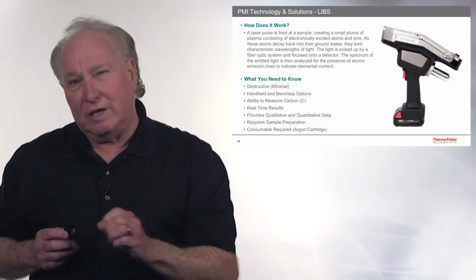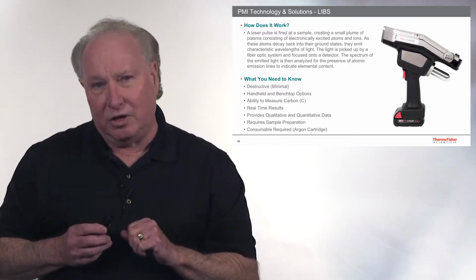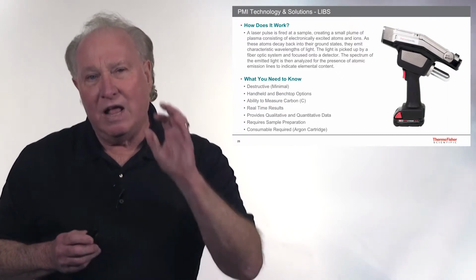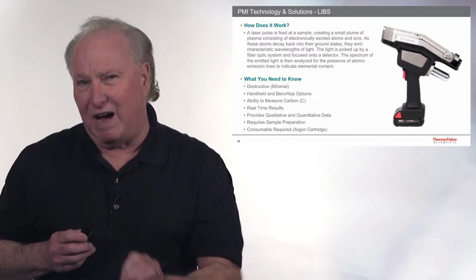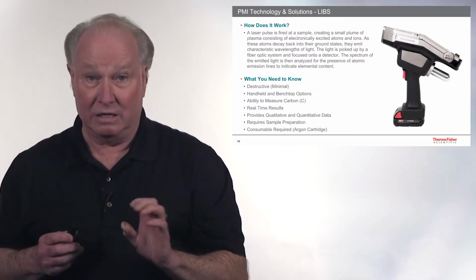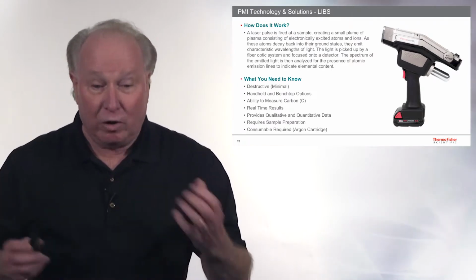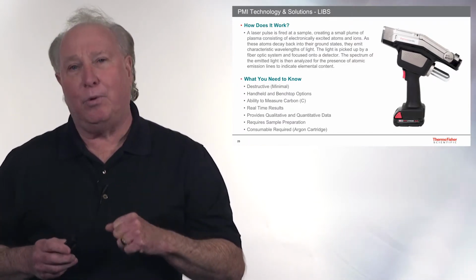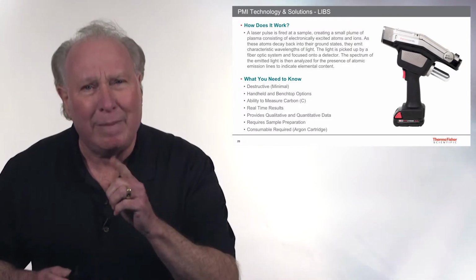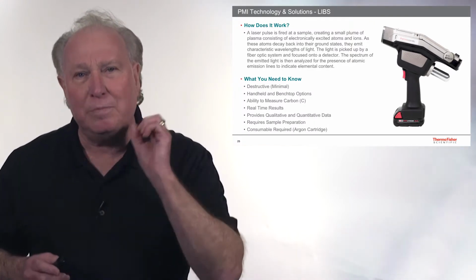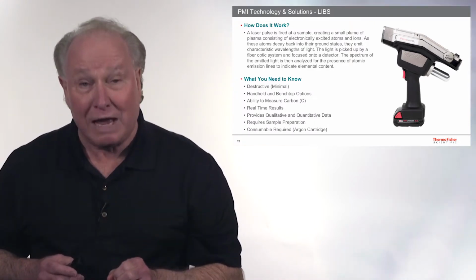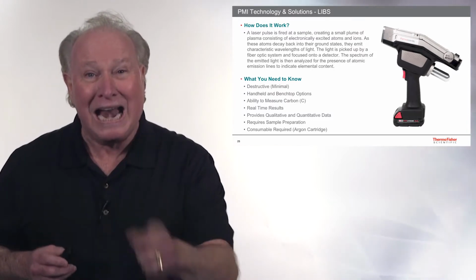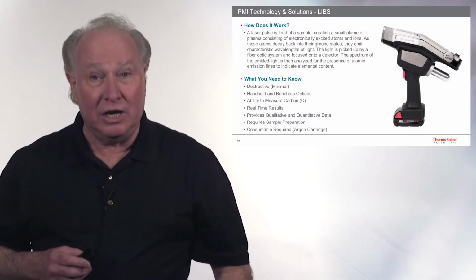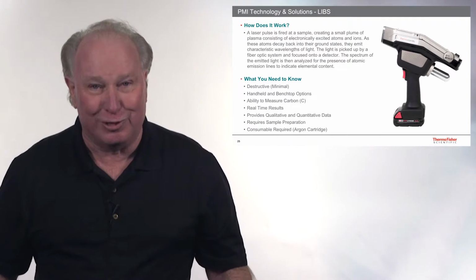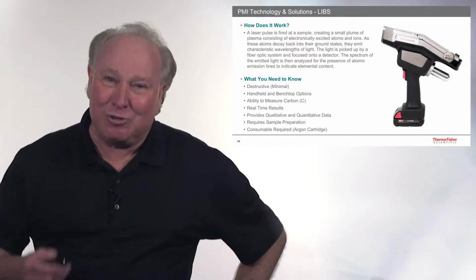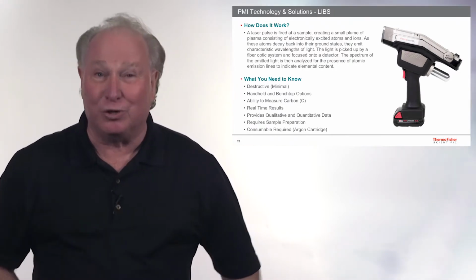Those detectors that detect them, there are 3 in the LIBS devices that are out there. They have charge coupled devices, CCD detectors in them. So they do a great job. Sample prep's very important. The clean argon, I might mention this, argon has to be laboratory quality. You know what that means? 99.999%. If you have any moisture in it, you won't get good results. And buddy, you spend time trying to get low levels of carbon, you want to make sure it's right.